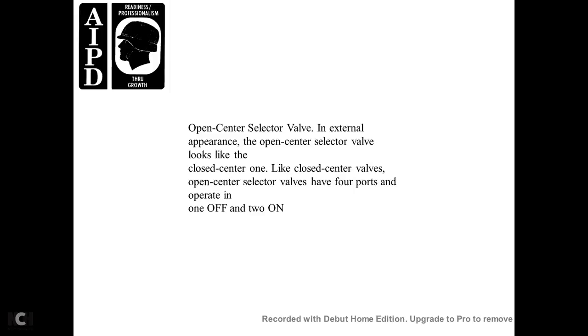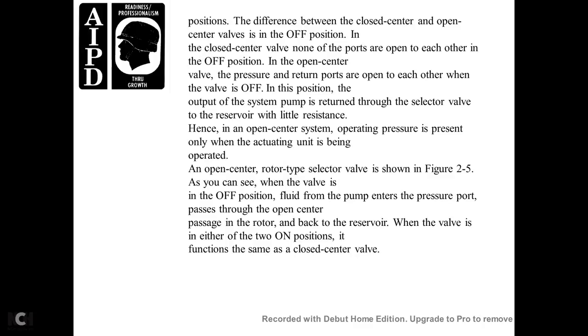Open-Center Selector Valve. The open-center selector valve looks similar to the closed-center valve and also has four ports with operating positions: on, off, and on. The difference between closed-center and open-center valves is that in the off position: the closed-center valve has none of its ports open to each other, while the open-center valve has its pressure and return ports open to each other. In the off position of an open-center valve, the output of the pump is returned through the selector valve to the reservoir with little resistance. Hence, in an open-center system, operating pressure is present only when an actuating unit is being operated.